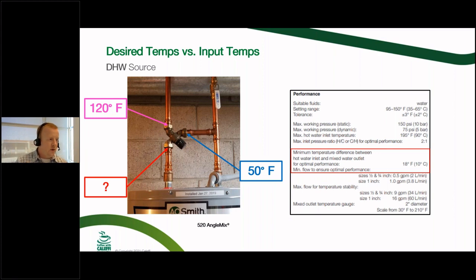People set the tanks to 120, and then all of a sudden they're not getting 120 out of the mixing valve. They're getting 112 or 105 or whatever, and they're like, what's wrong with this thing? Well, again, you need to make sure that you're putting in a slightly higher temperature than what you're looking to get out of that mixing valve. I think this is a win-win for everybody, because by increasing the temperature of the tank, you're going to have the ability to extend the capacity of the tank. You're also going to have the ability to kill off bacteria, Legionella bacteria, in that tank by running it at a higher temperature. It's a win-win all around. Okay, so make sure you're meeting that minimum temperature difference from hot inlet to mixed outlet.